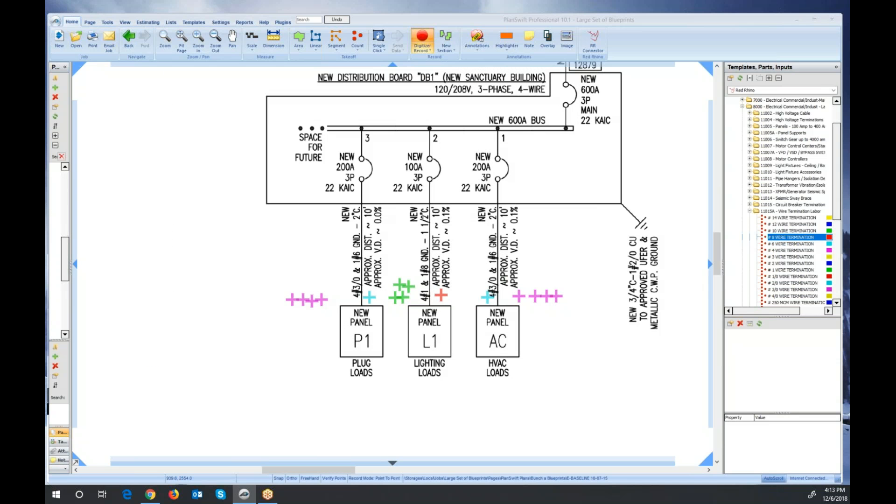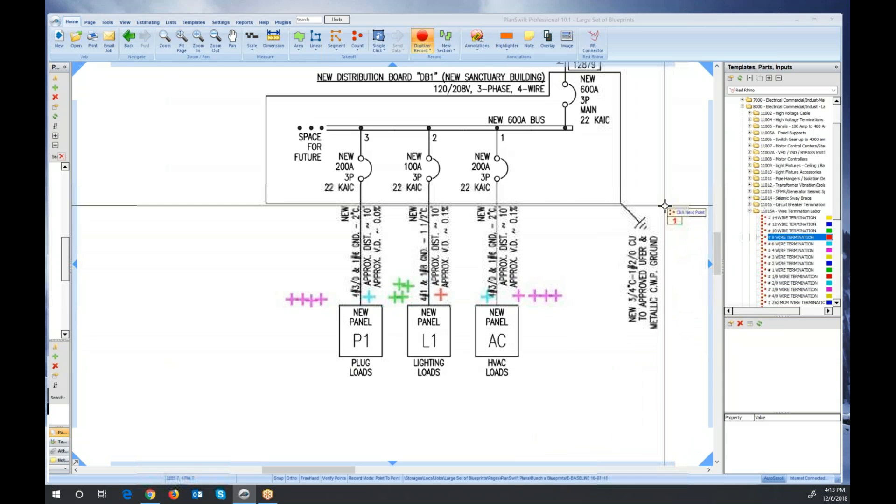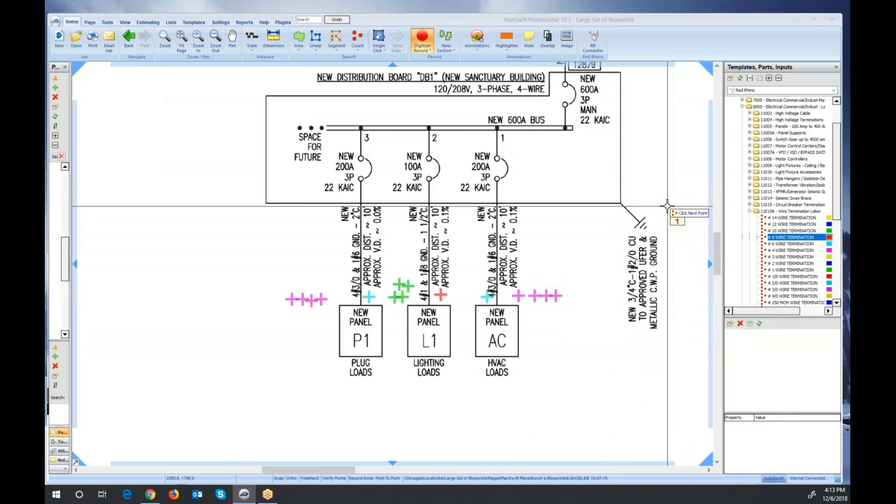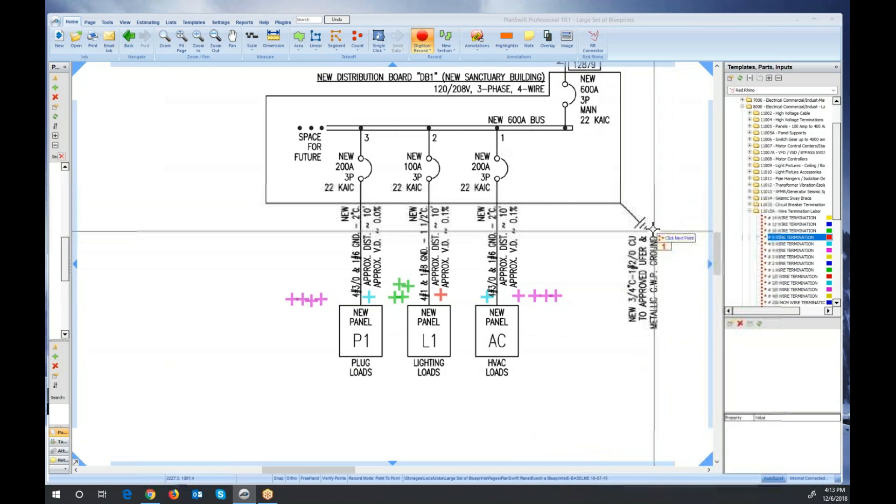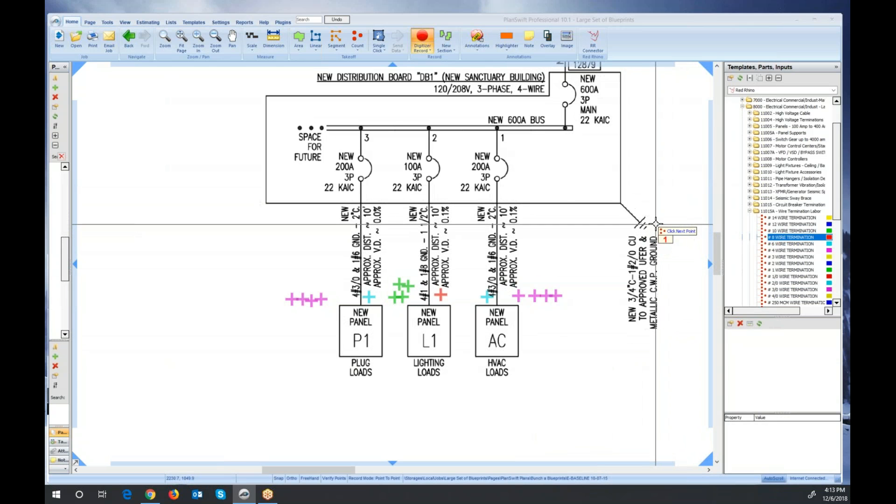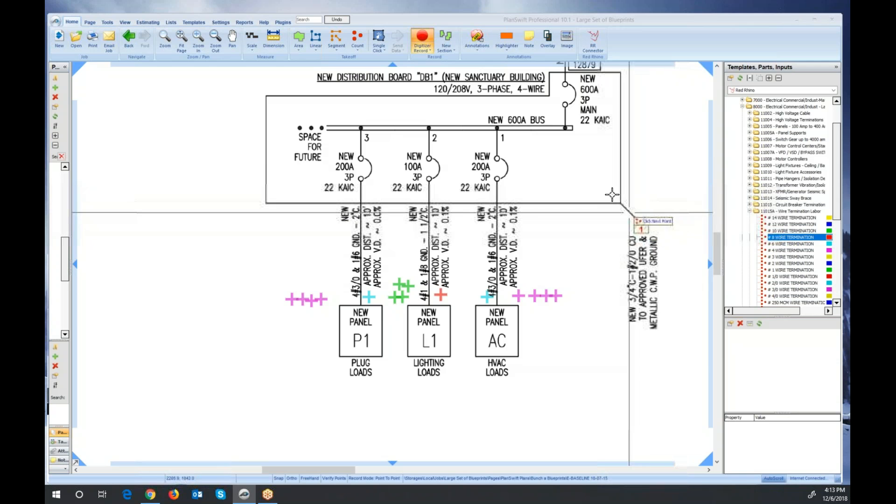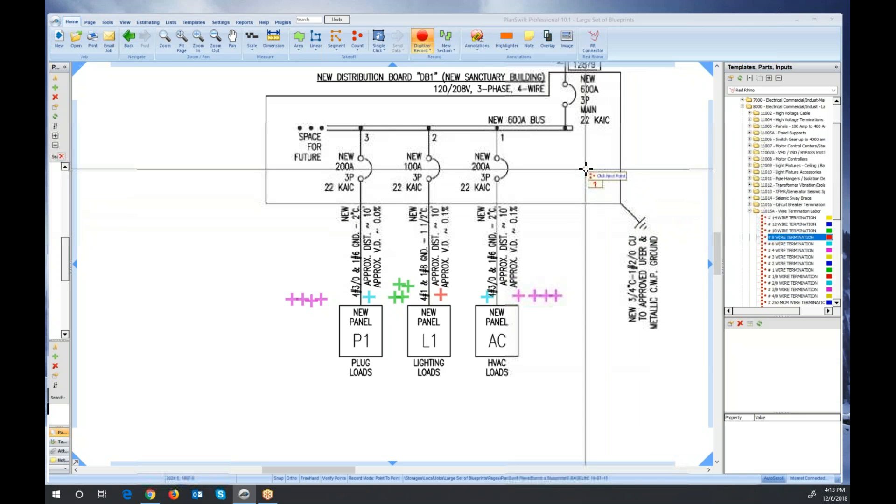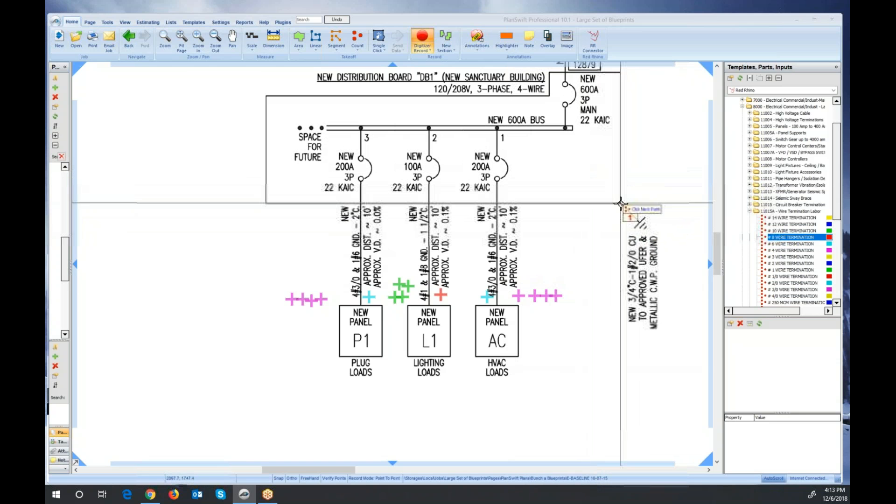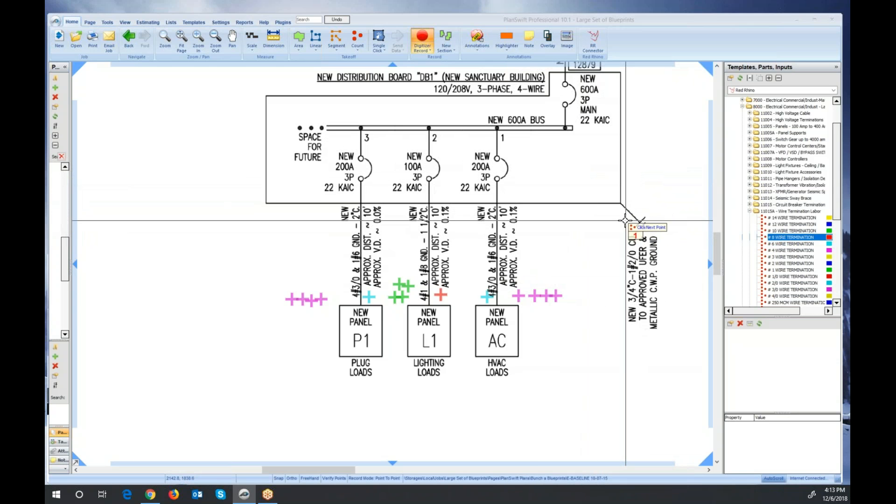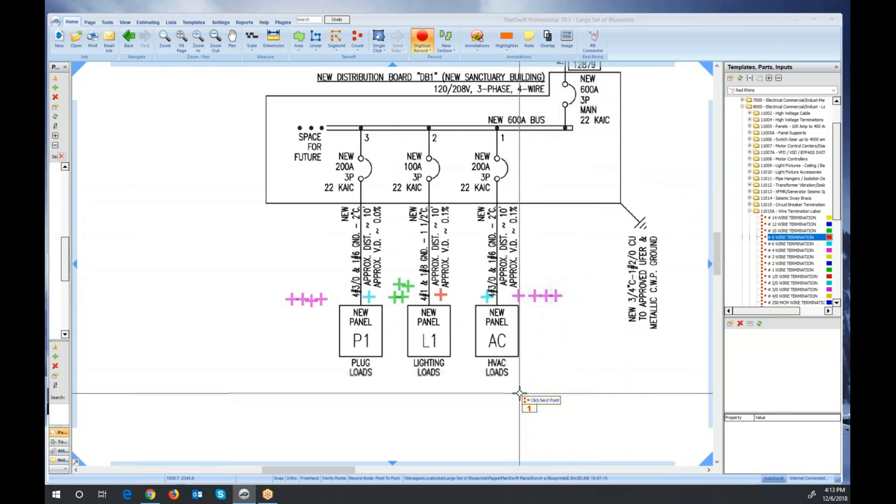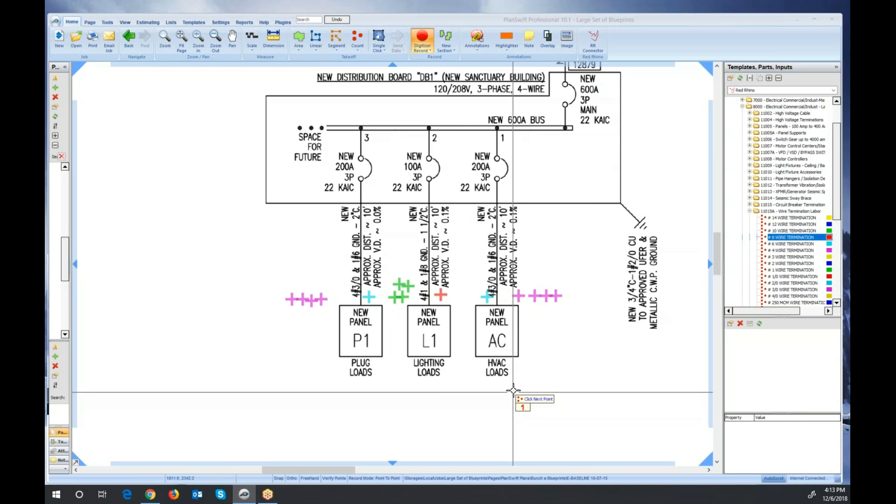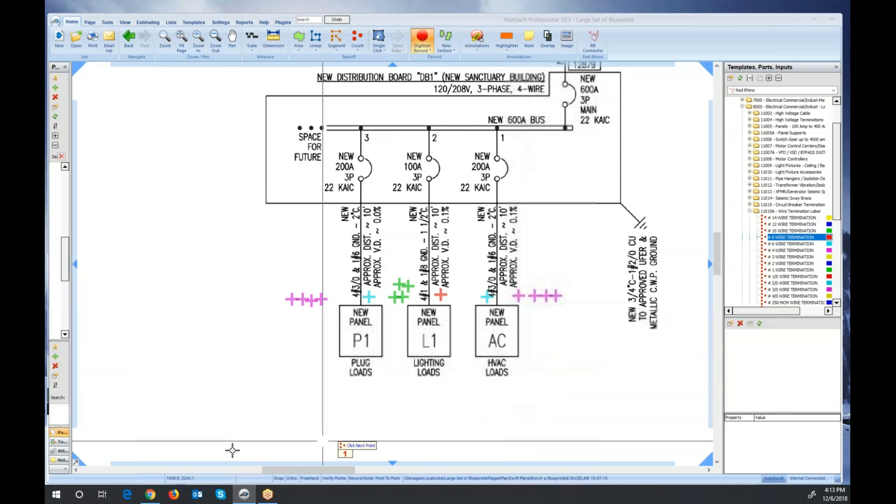Before I move on, another example is this ground right here. It says that it's a three-quarter conduit with one number 2-aught. I'm not going to input this, but this 2-aught has to be terminated at two ends. One in the service or panel, and one at the ground rod. So I would include that also. It's important to account for that labor because it really adds up if you leave it out. It takes time.